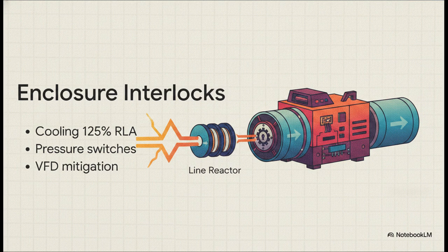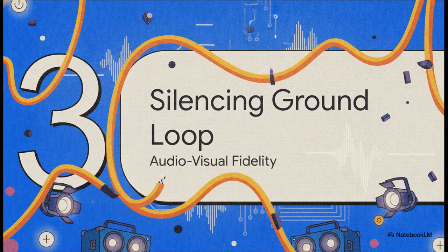And if that fan uses a variable frequency drive, you have to install line reactors to shield the sensitive projection power feeds from the fan switching noise. Section 3. Silencing the ground loop.